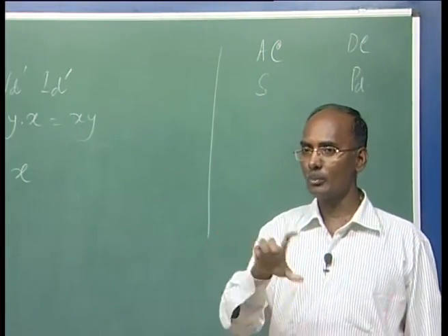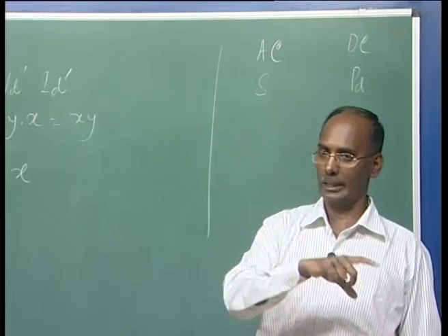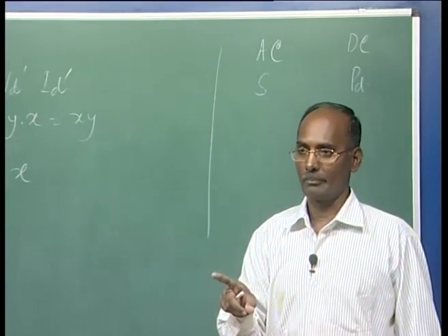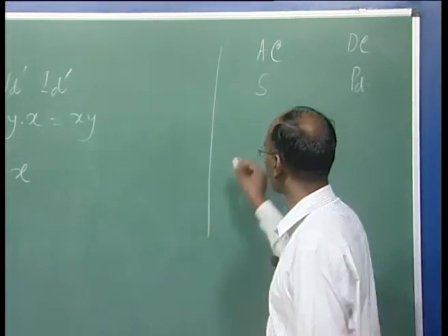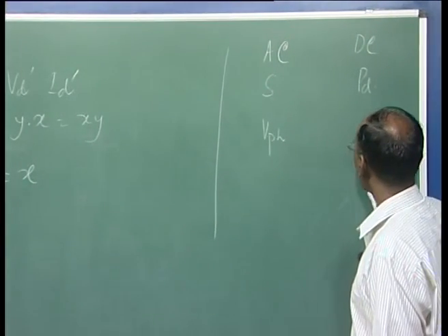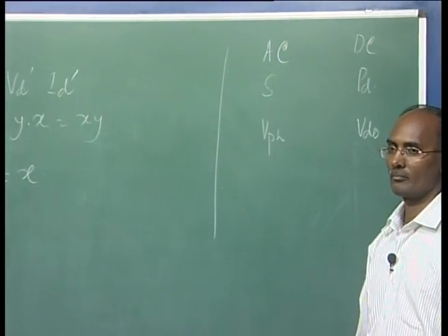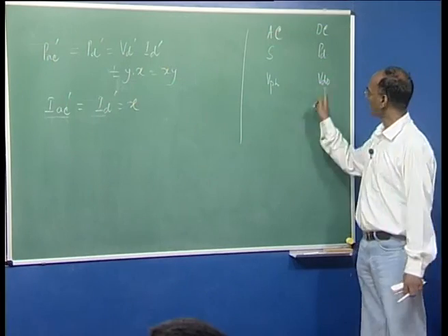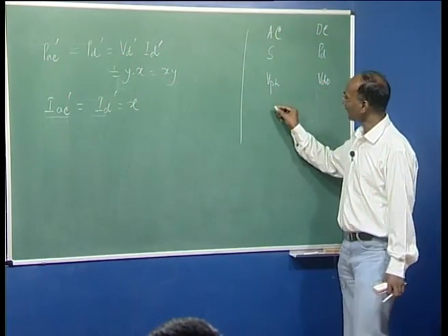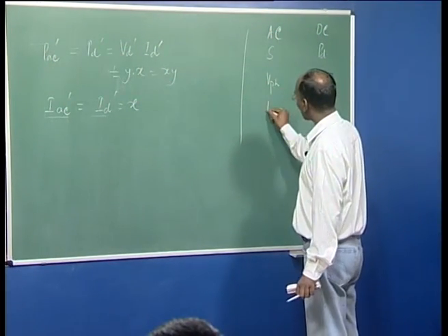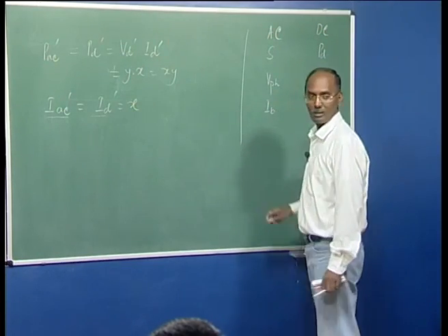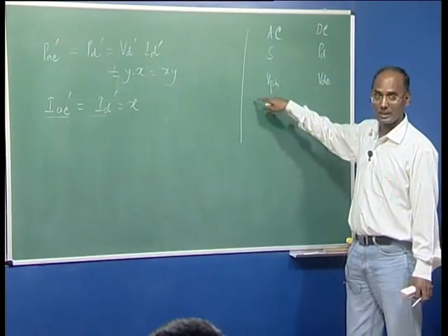Now you have to see what the voltage difference is between the rectifier end and this end. That will not be the same, because the base value on this side is your V phase base value, but on this side it is your VDO. Just you see it. So here we have to calculate what your current base will be based on these two AC side values.